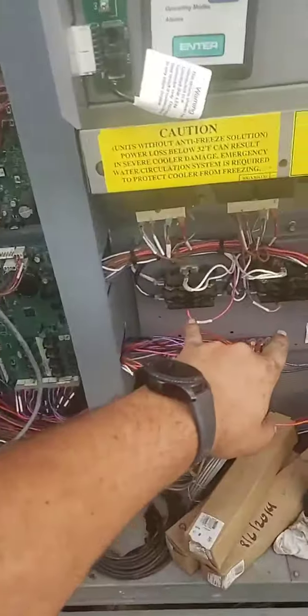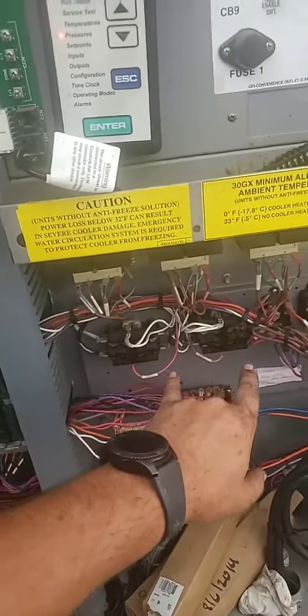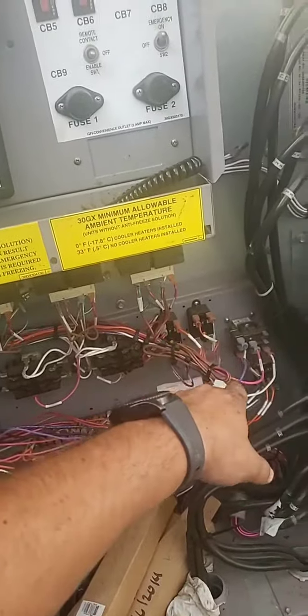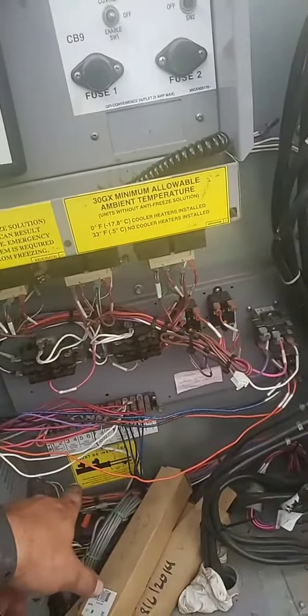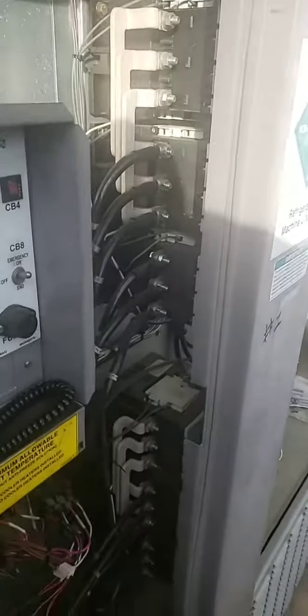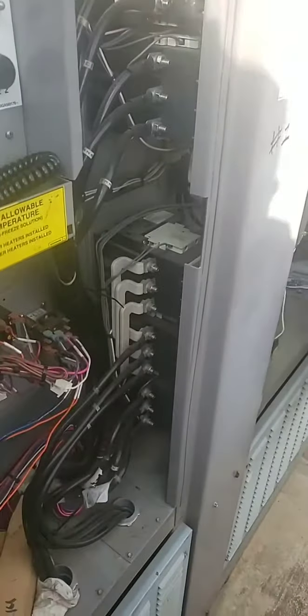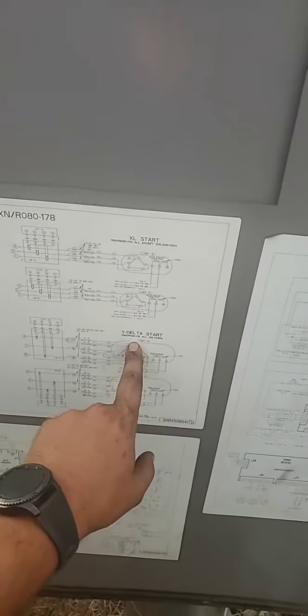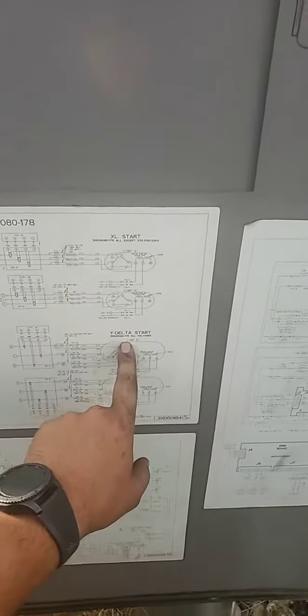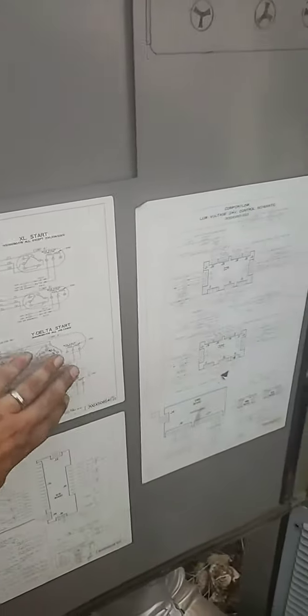Shows you the motor wiring. These are part of your heater contactors, your water pump, all that's coming through here. Your EMS communication. If you look back in there, those are your compressor contactors. So compressor A, compressor B. Yes, they are doubled up, double lug. Right now, they're wired in as a wye delta start. That's what they're set up for at the moment. That just depends on how your incoming voltage is, depends on how they'll have to set up that power.